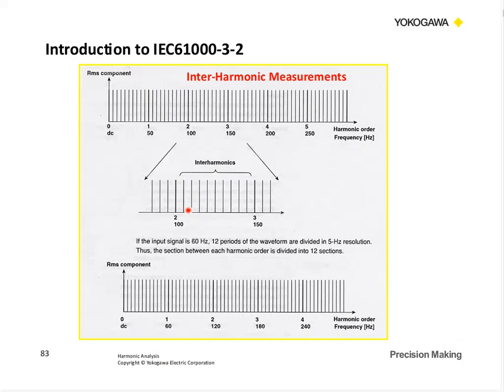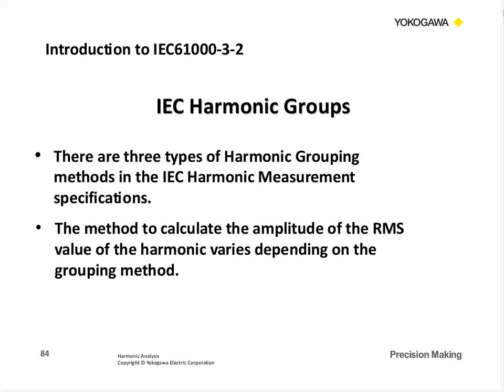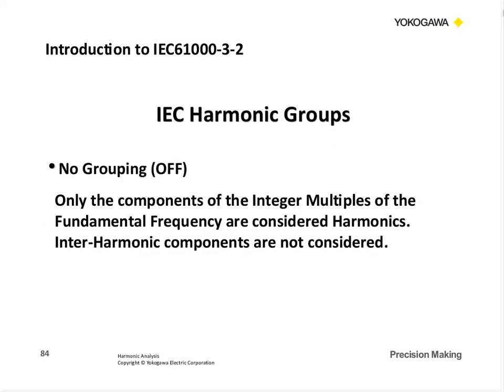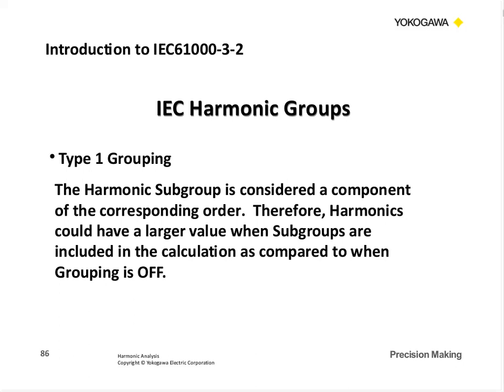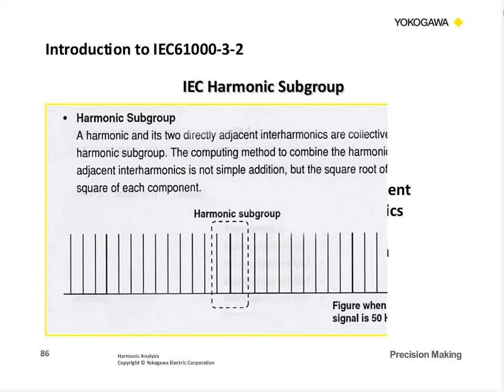And these interharmonics are interesting the way the IEC has defined them. So it is looking for harmonics other than just the fundamentals or the integers, like the second, third, fifth. Okay, it looks at the ones in between. And it breaks it down into what they call grouping. So you have to calculate the amplitude in these various groups. So it's a complicated measurement, and we do have one of our products that will do this IEC compliant testing. If we get into some questions, we can try to help you on that.